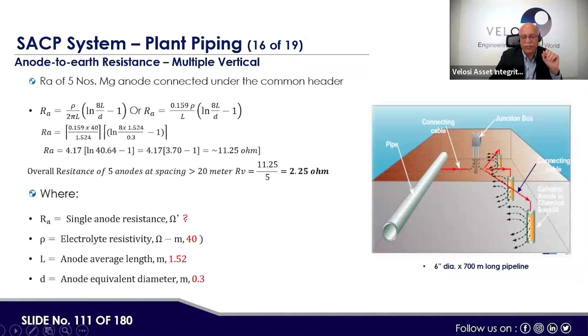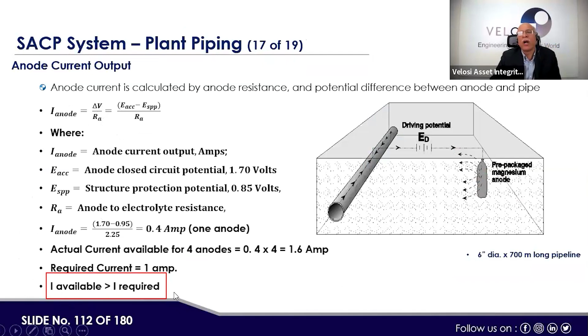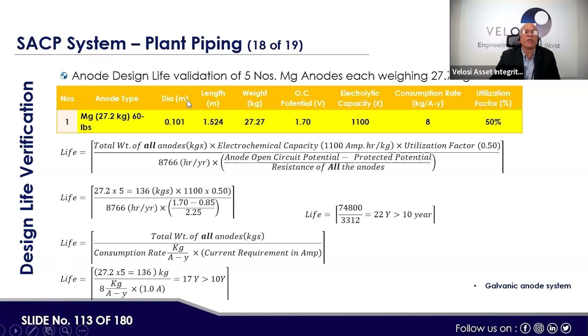Then the anode current output, I anode, is equal to delta V over RA, and if the output available is greater than required, then it is considered acceptable. Next is the anode design life validation of 5 magnesium anodes, each weighing 27.7 kg. This is the formal equation and the calculations are made.